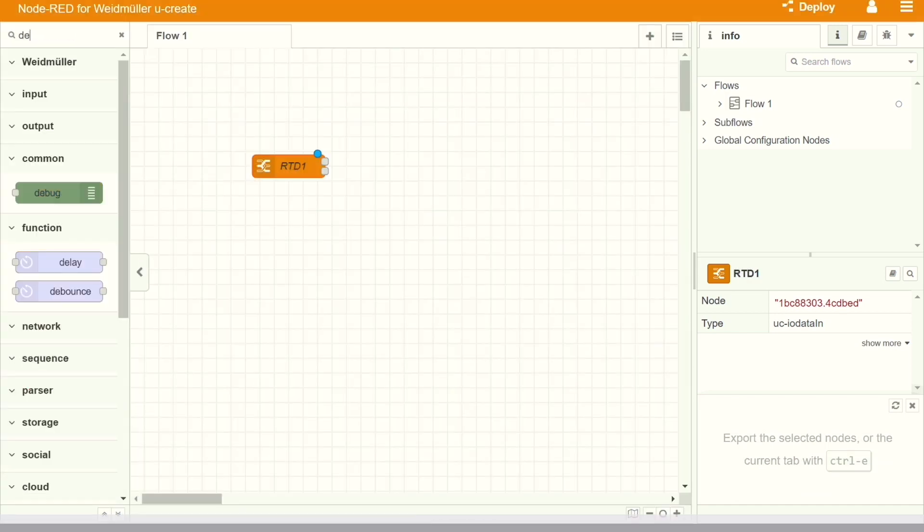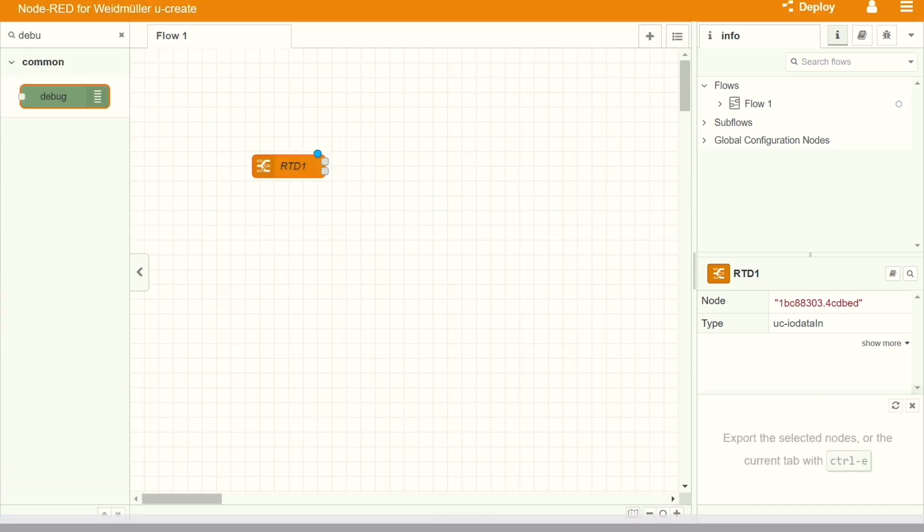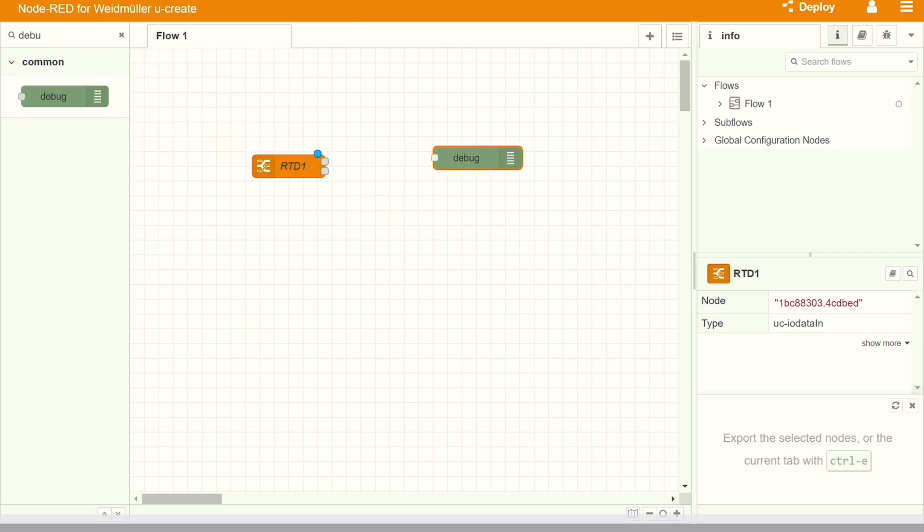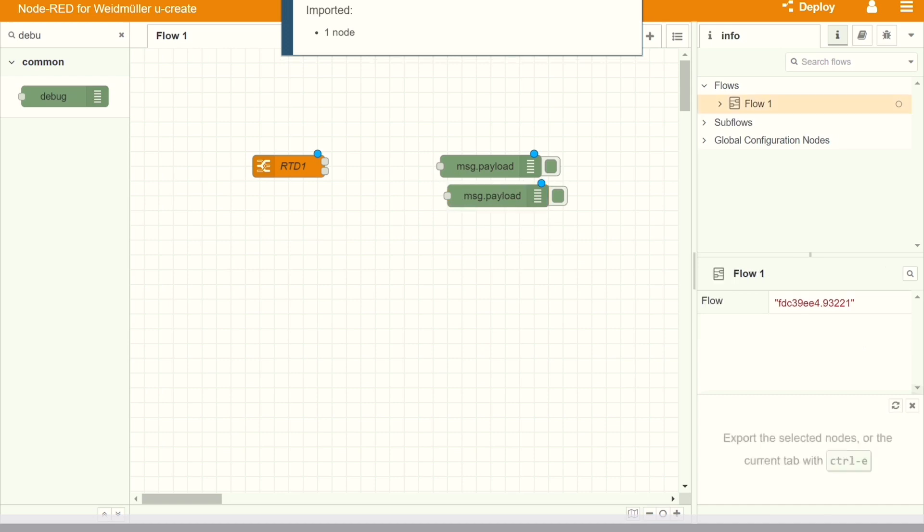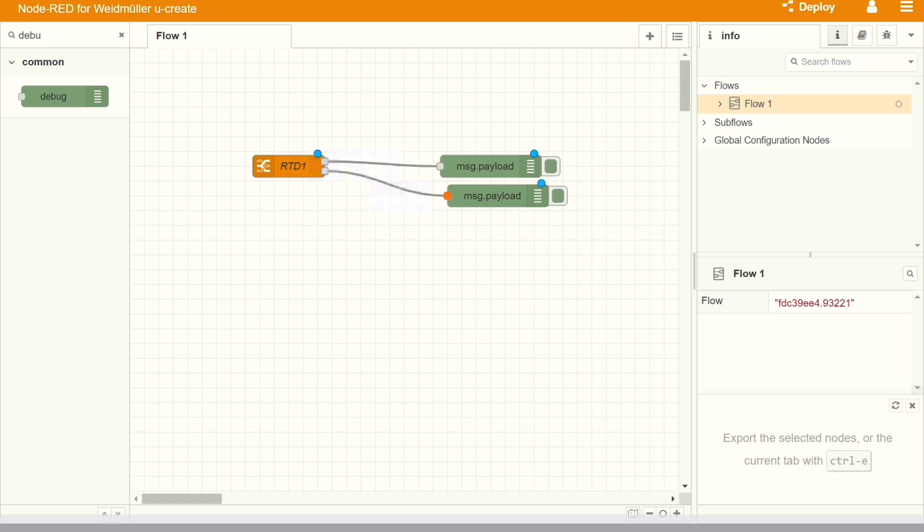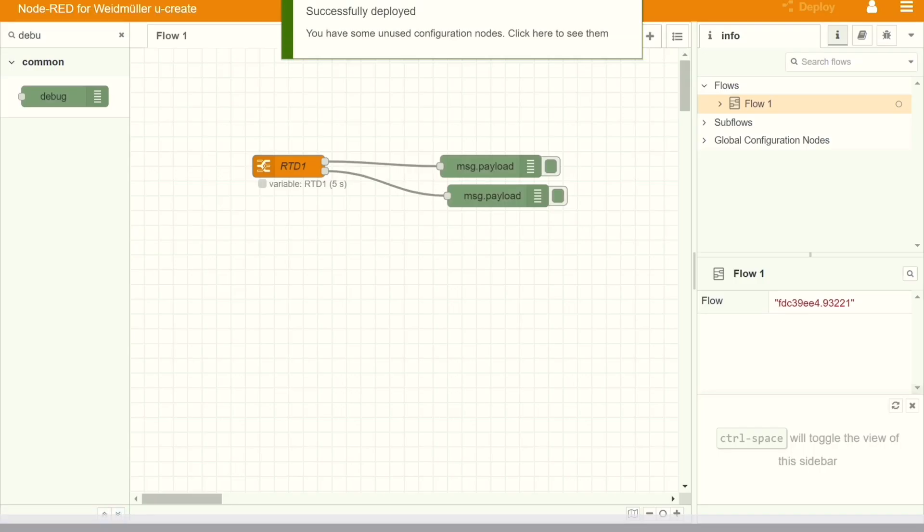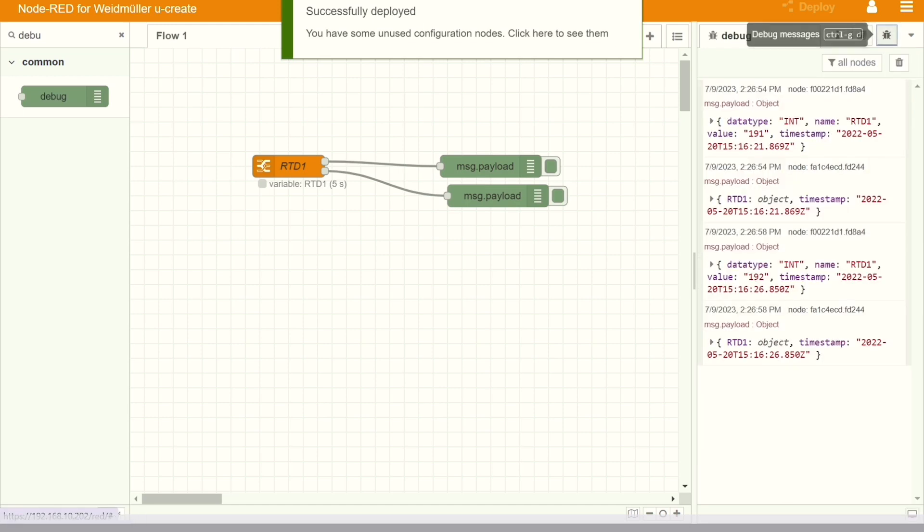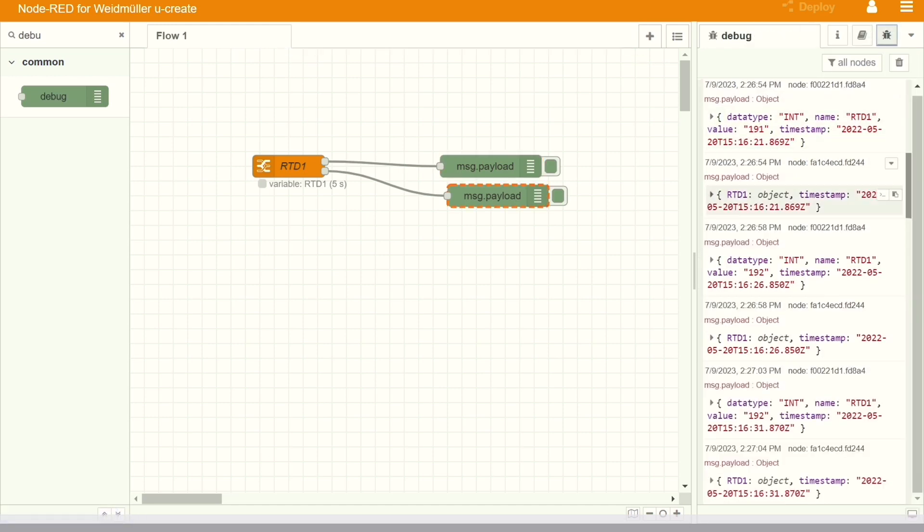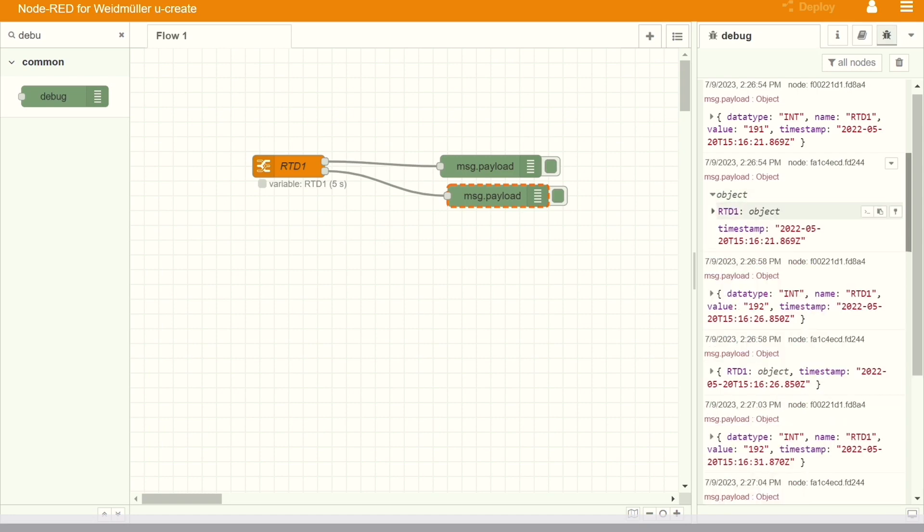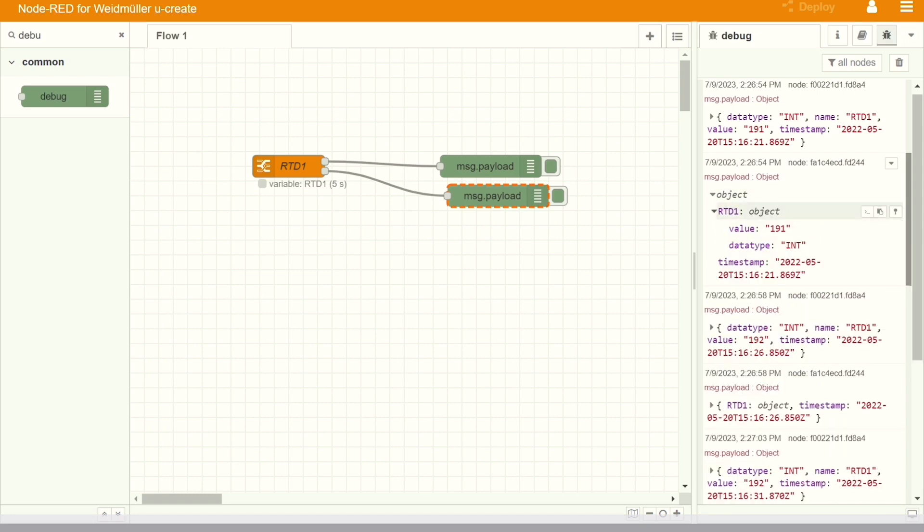We need to drag and drop the particular nodes and configure the variable which we want to read it from the IO channel. In this particular, I am reading the RTD. Now I will put a debug node and then when we connect the process data and the status data, both are coming. When we deploy the code, we can see that the data in the debug node, it is showing in particular structure, value, timestamp.